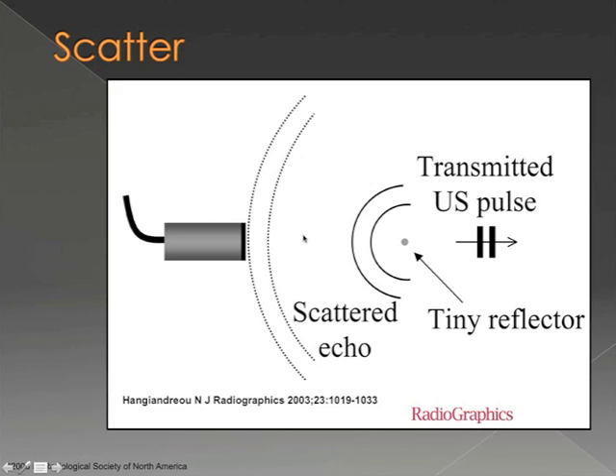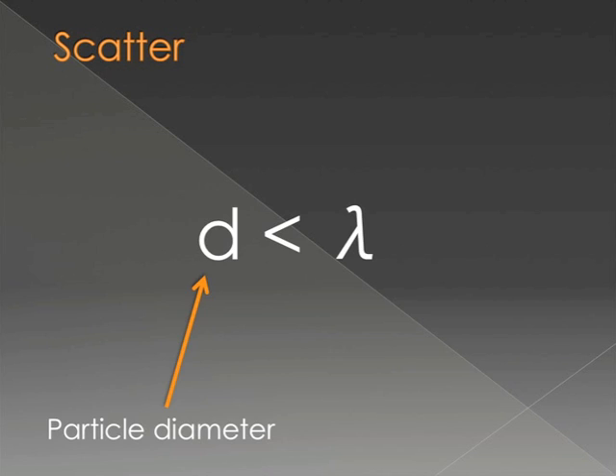Finally, probably the most important interaction with tissue is called scatter. Your sound beam is emitted from your transducer, hits a tiny reflector, and causes sound waves to be scattered off in numerous different directions — represented here by the two curved lines. The dotted lines show that over time, those scattered echoes are reflected back towards the transducer. Whether or not something is scattered depends on the particle diameter, which has to be less than the wavelength. Scattered echoes and interference patterns from scattered echoes are predominantly what leads us to see the echo texture for things like the liver, muscle, or kidney and how those are different. So scatter really is probably the most important tissue interaction for image formation.